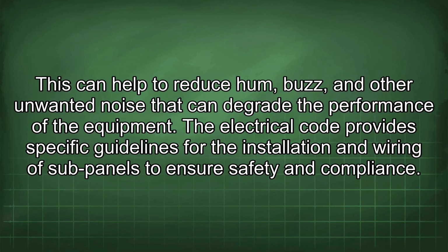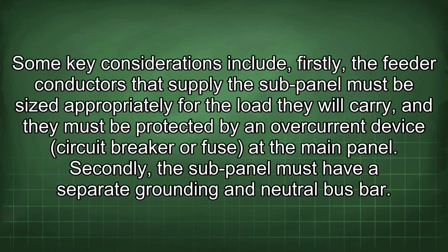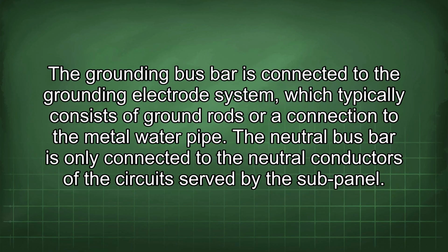The electrical code provides specific guidelines for the installation and wiring of sub-panels to ensure safety and compliance. Some key considerations include: firstly, the feeder conductors that supply the sub-panel must be sized appropriately for the load they will carry, and they must be protected by an overcurrent device, circuit breaker, or fuse at the main panel. Secondly, the sub-panel must have a separate grounding and neutral bus bar. The grounding bus bar is connected to the grounding electrode system, which typically consists of ground rods or a connection to the metal water pipe. The neutral bus bar is only connected to the neutral conductors of the circuits served by the sub-panel.